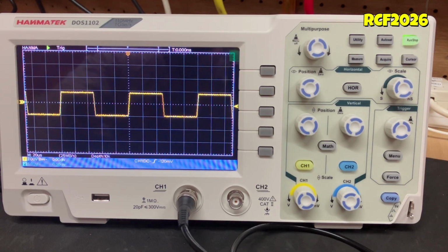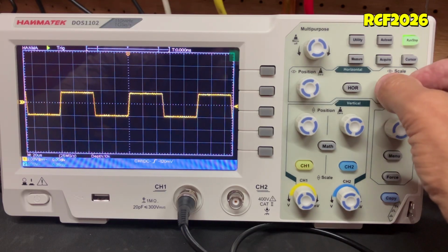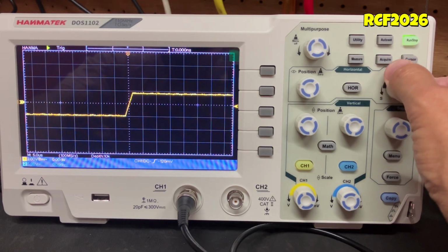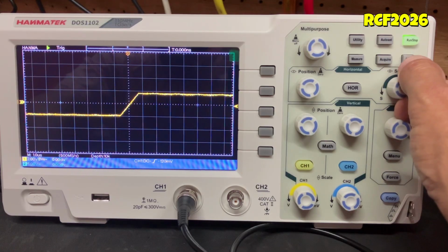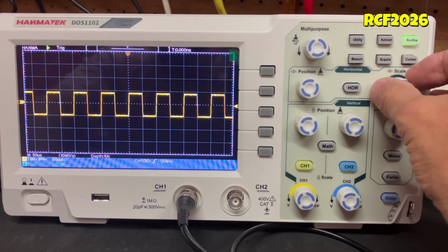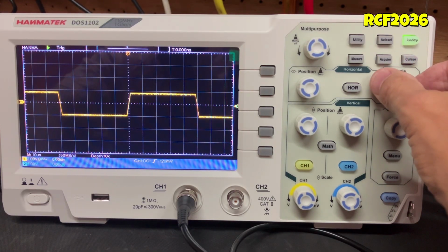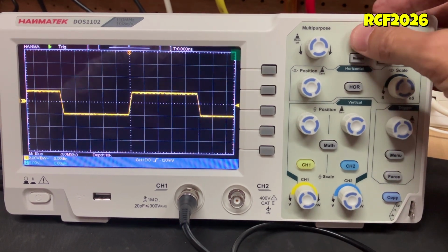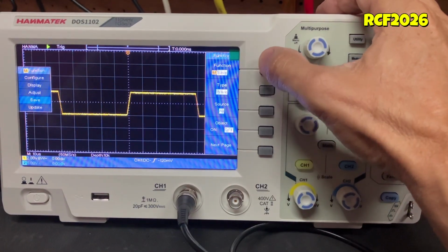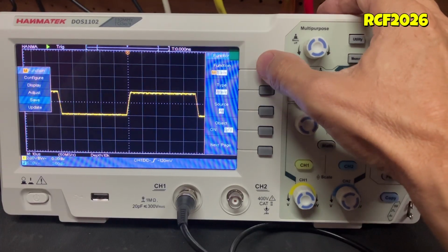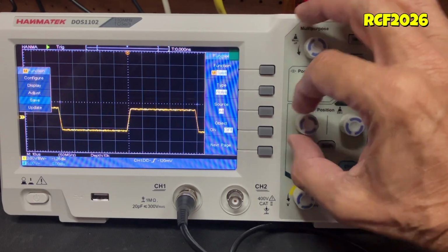The trigger controls are also important when working with captured waveforms. They allow you to adjust the trigger position and settings so the oscilloscope can reliably lock onto the waveform. Correct trigger adjustment helps produce a stable and easy-to-read display, which is especially useful when measuring repetitive signals or examining changes within a waveform.